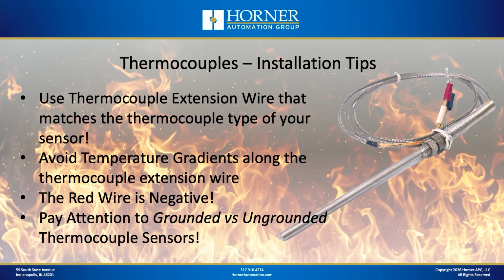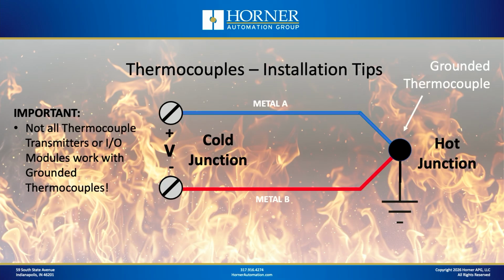Another thing you have to pay attention to with thermocouples is grounded thermocouples versus ungrounded thermocouples. What's that all about? Well, if the hot junction is electrically conductive with the sheath that it's installed in, that is called a grounded thermocouple, because if that sheath is installed on a machine and touches metal, if you will, it's going to be conductive to that measuring junction. And there's a reason why in some applications they want it that way. That's because if you do have a grounded thermocouple, they will respond even faster than an ungrounded thermocouple.